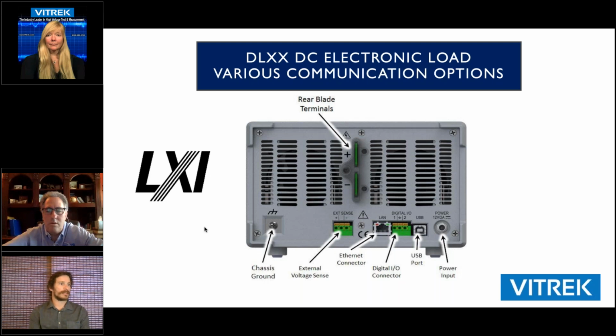So on the rear panel, like I said, there's the blade terminals with a cover to go over them. That's where you're going to get full specs, best performance, higher current ratings. You can simply bolt through those with a ring lug and a bolt. There's also external voltage sense, if you're concerned about voltage drop through your test leads and you're trying to make an accurate measurement, you may want to use those.